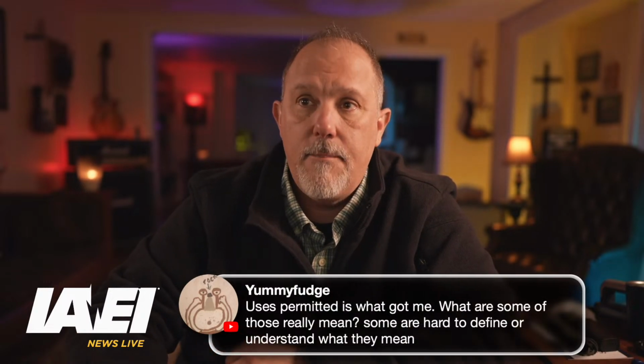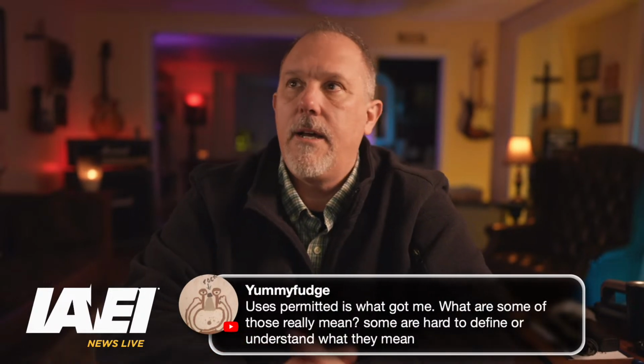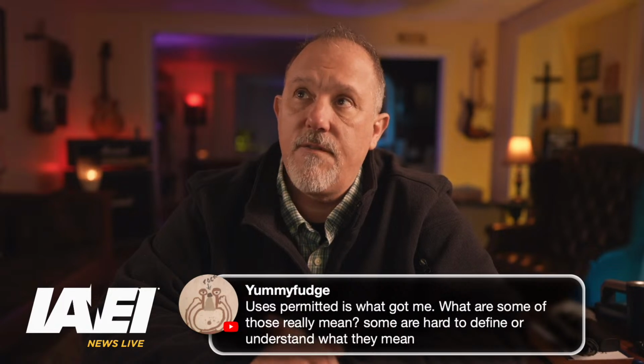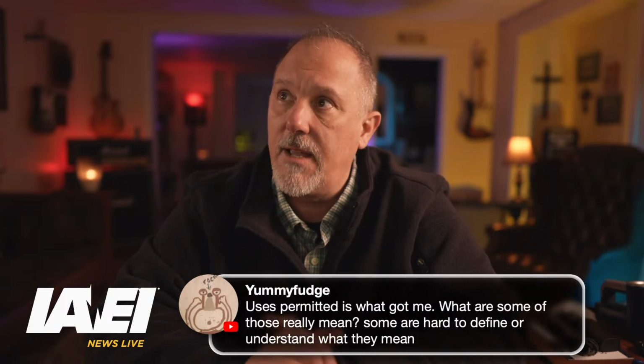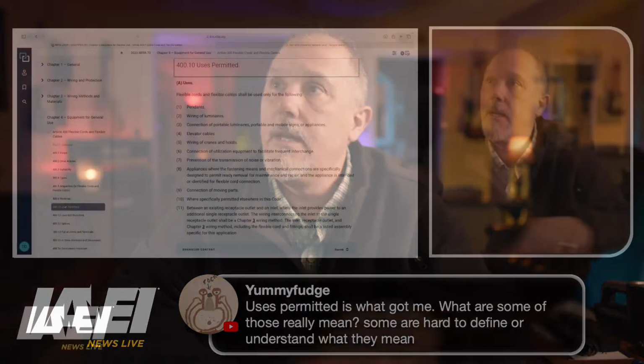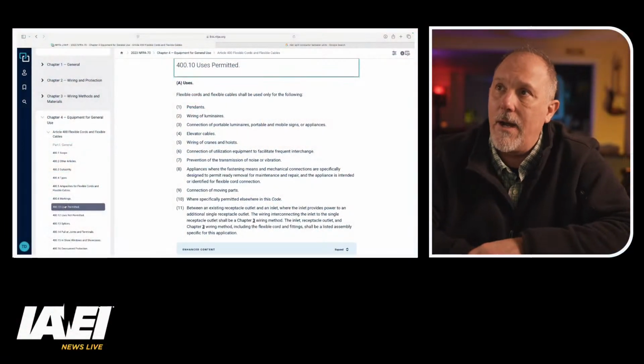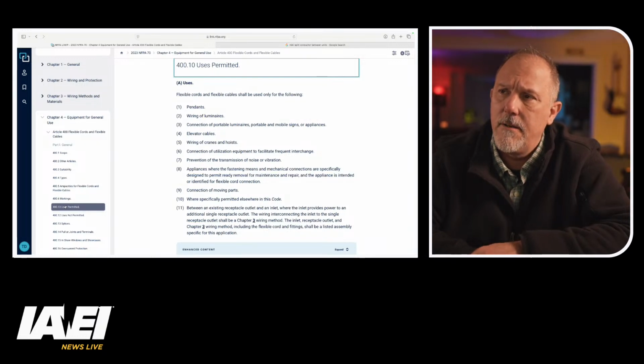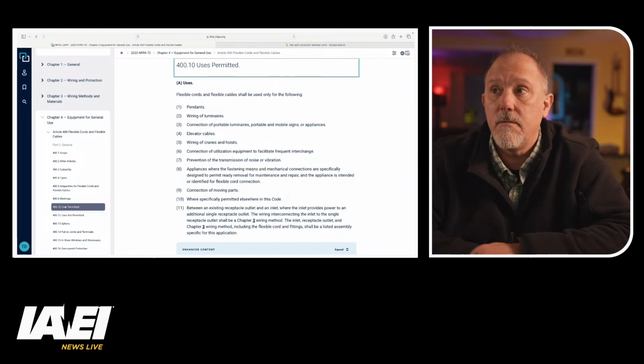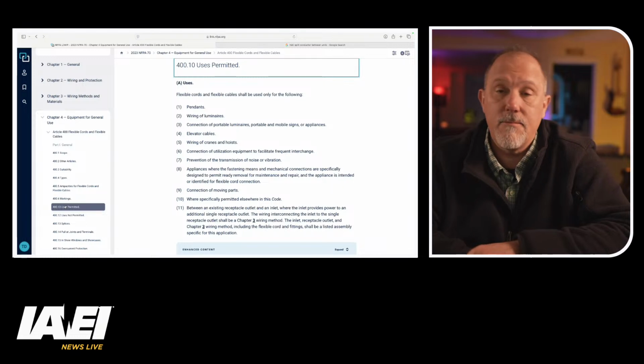But Yummy is saying flexible cords in 400.10, it says flexible cords and cables shall be used only for the following: pendants, wiring of luminaires, connection of portable luminaires. We've got elevator cables, so those seem pretty straightforward. Appliances where the fastening means and mechanical connections are specifically designed. Connection of moving parts where specifically permitted. That's a pretty generic one.